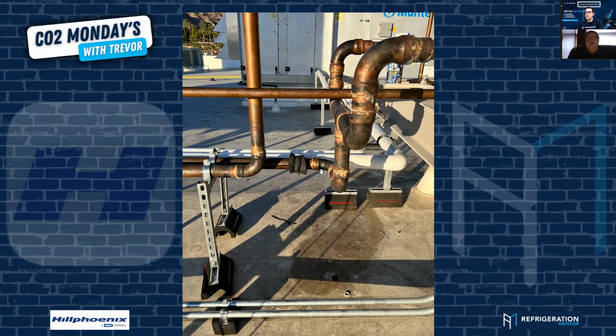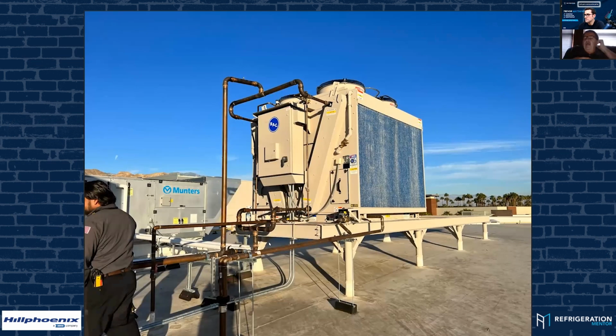Okay. So where should this be located then? Now, pick a side. If it's two drop legs, pick the left or the right. Me, if it's a BAC, I like to use the left side, because that's where you'll see that sensor, that wire going up to the middle of the condenser on the right. Nope, go up to the right over there. There you go. Nope, back over there. Yeah, next to the tag, you see that blue and white tag? That's our pad temp sensor. Oh, right over here. Right there to the left, that little gray box, 4x4.